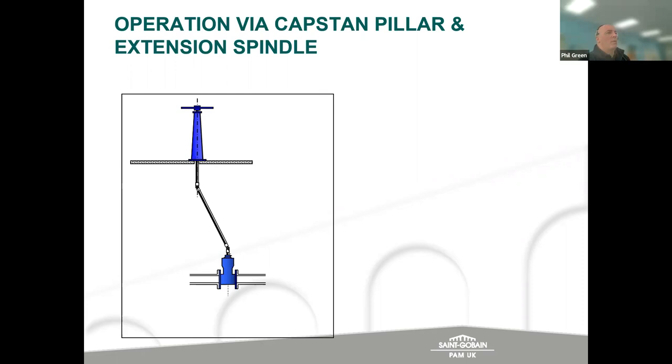And this provides a bearing for the spindle at the point where operation generates side thrust. So the pillar can also be provided with a position indicator and various parts of kit and guide brackets that you can use to accommodate this particular installation practice. So the brackets are usually arranged to support the spindle from an adjacent wall and have a plain bearing surface, or be bushed with a suitable material, gun metal, nylon, etc.